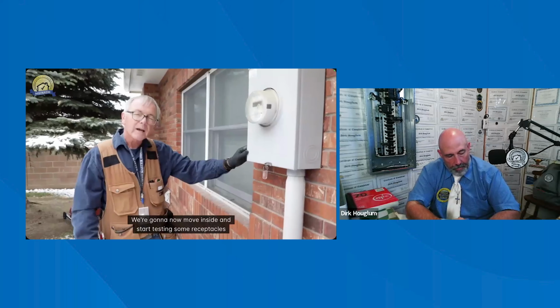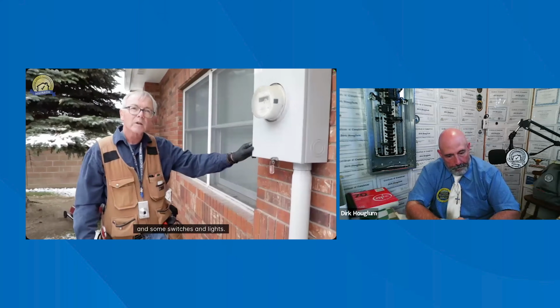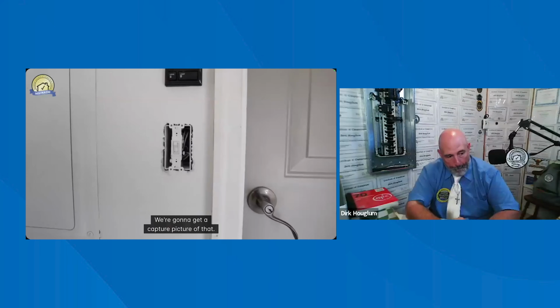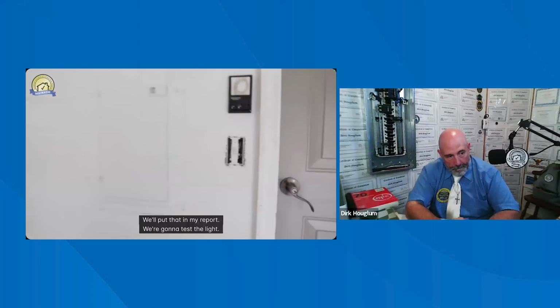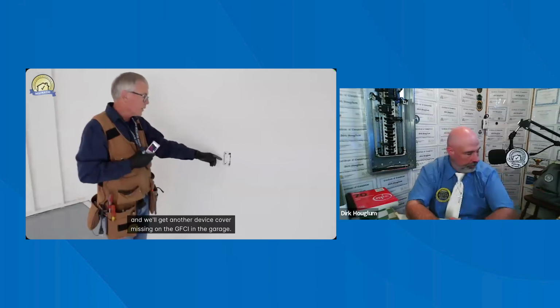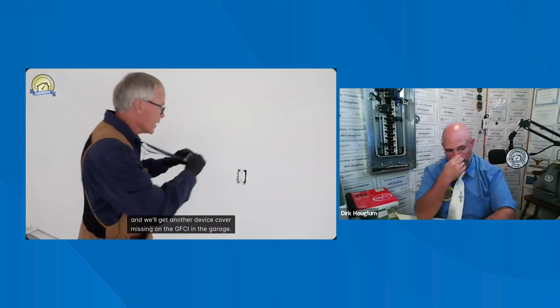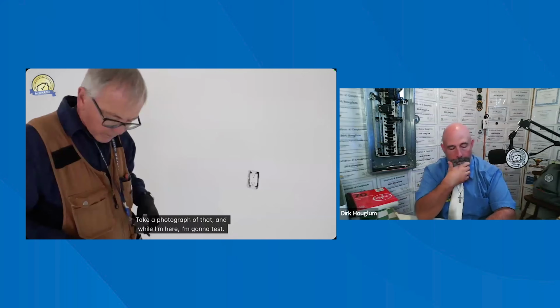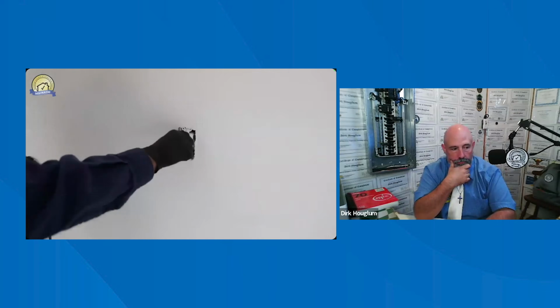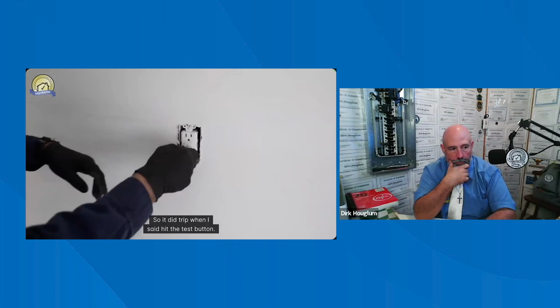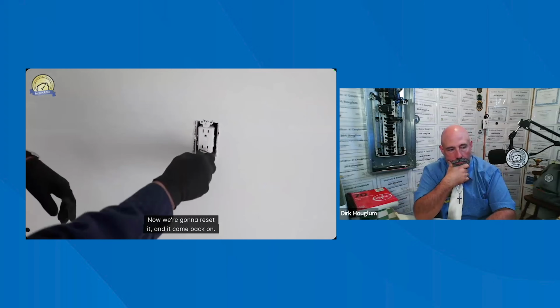We're going to now move inside and start testing some receptacles, switches and lights. Okay, now we're inside. We're going to test some receptacles and switches. On this one here in the garage, the first thing I notice is the device cover is gone. I'm going to capture a picture of that. We'll put that in my report. I'm going to test the light. That seems to work fine. We're going to move down the wall here, and we've got another device cover missing on the GFCI in the garage. Take a photograph of that, and while I'm here I'm going to test it. It did trip when I hit the test button. Now we're going to reset it, and it came back on. So that part looks okay.